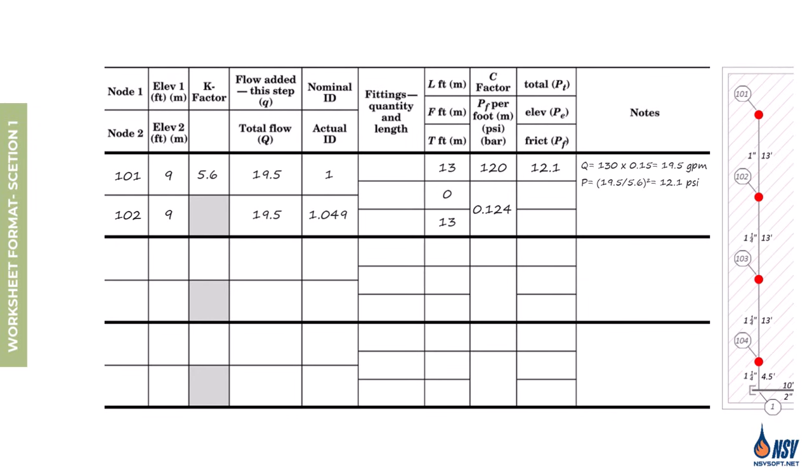We should record this calculation in the notes cell. In the middle cell, we calculate and record the pressure loss or gain caused by elevation changes. Since the start and end nodes of this segment are at the same elevation, the pressure change is 0. In the lower cell, we calculate and record the minor and major losses.